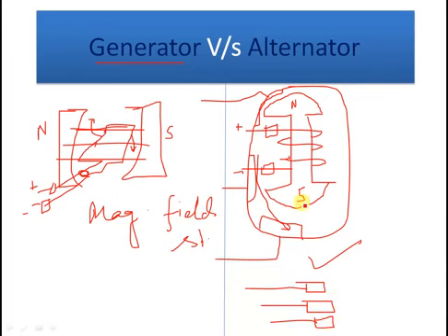Whereas in case of excitation, in case of rotor, you only have to give two of these. So only by connecting two brush and slip ring arrangements you can do this. Other than this, there are certain economical advantages on the design basis. To make the three-phase conductors rotate is not that economical. In case of high power demand, it is always recommended that the field is rotating, while the armature conductor, so you can say the output conductor, is stationary.